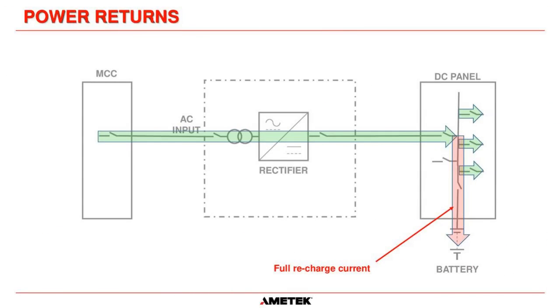And then when power comes back on again at the MCC, the charger goes back to powering the load circuits, and now it is also supplying power to the battery. Depending on how discharged the battery is and the size of the battery will depend on how much current is flowing to the battery at this point. If it's a very large station battery, it could be hundreds of amps going into the battery to get it recharged, depending on the design of the system.